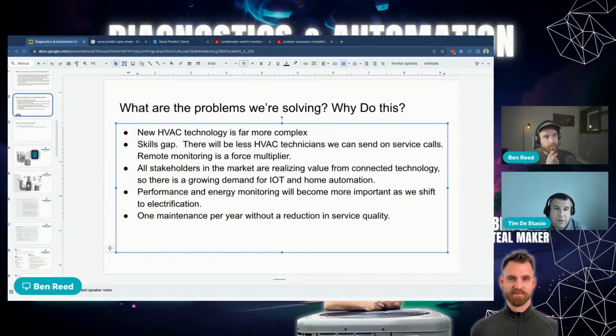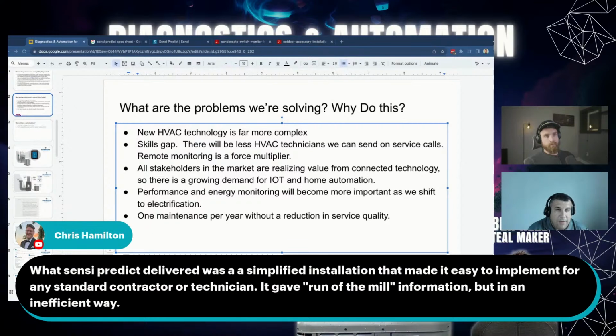I think a lot of the faults that these systems can detect, that's the whole point, you're getting 90% of your diagnostics done before you even get out there. So if you've got a system that can read power factor, and it starts seeing a degradation of power factor over time, then you know probably the capacitor's going bad. Well, it alerts you and you send a technician out there. Well, that's a really easy thing to diagnose in the field as well as remotely.